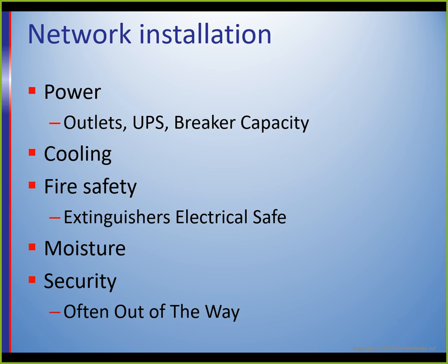Power. How many outlets do we have? Where are the outlets? Are there a sufficient number of outlets? Do we have a UPS? What's the breaker capacity? Breaker capacity here, because if we use power over Ethernet, it's not just going to be the power of the switch. It's going to be the power that the switch consumes, as well as the power that the switch delivers to the devices. So you have to take that breaker capacity into consideration. A lot of 15 amp breakers, and the PoE switches are a little bit higher, so you may have to go with a higher level breaker on these things.